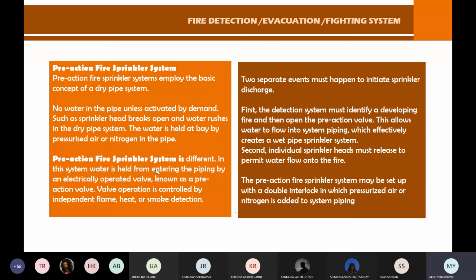First, the detection system must identify a developing fire, and then open the pre-action valve. This allows water to flow into the system piping, which effectively creates a wet pipe sprinkler system. Second, individual sprinkler head must release to permit water flow onto the fire.